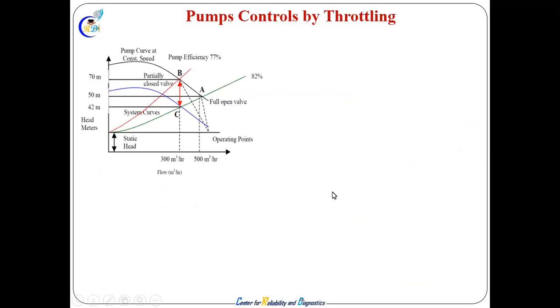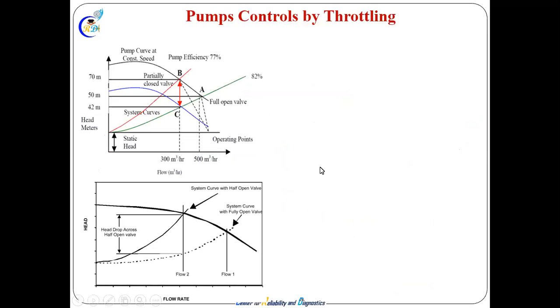So in speed variation, when you throttle, when you want less energy with throttling or want to reduce the flow, what happens? From point A it will go to point B, and on this system curve, which is at 82% efficiency, it will go to a lower efficiency. But you want less flow, from 500 to 300. It is a 500 pump, but you want 300 cubic meters per hour, because the process requires only that much, the operation paper says so. So what do we do? We throttle.